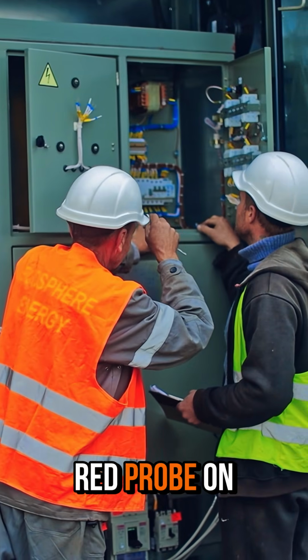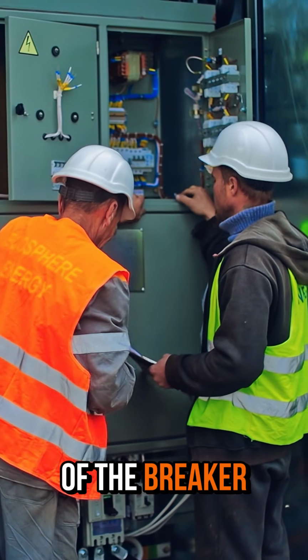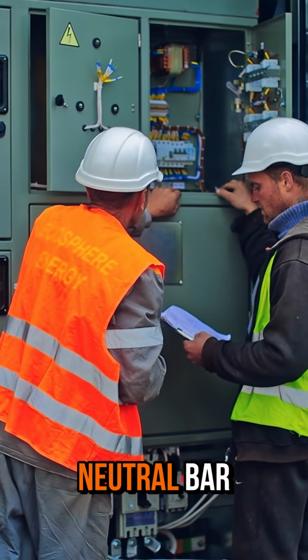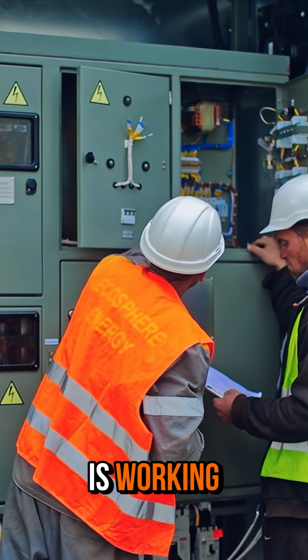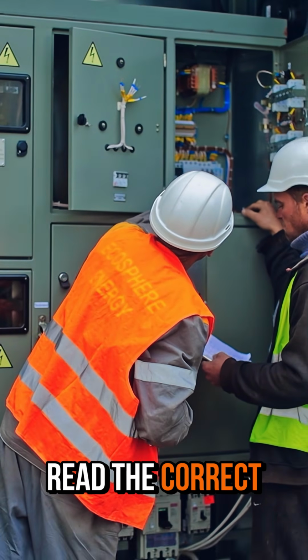Carefully place the red probe on the screw terminal of the breaker and the black probe on the neutral bar. If the breaker is working, your multimeter should read the correct voltage.